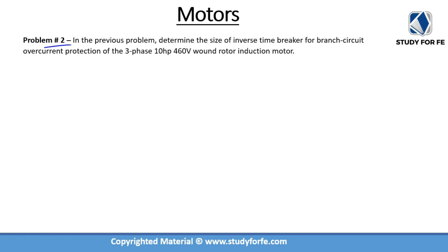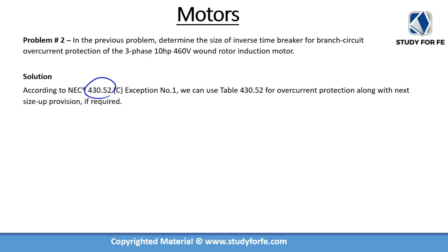Problem number 2 builds upon the previous problem and asks us to determine the size of an inverse time breaker for branch circuit overcurrent protection of the 10 horsepower motor. Section 430.52 deals with branch circuit overcurrent protection, and 430.52(C) exception number 1 allows us to use table 430.52, which tells us what percentage to apply to the FLC. If that value is not a standard device rating, we can go to the next size up.